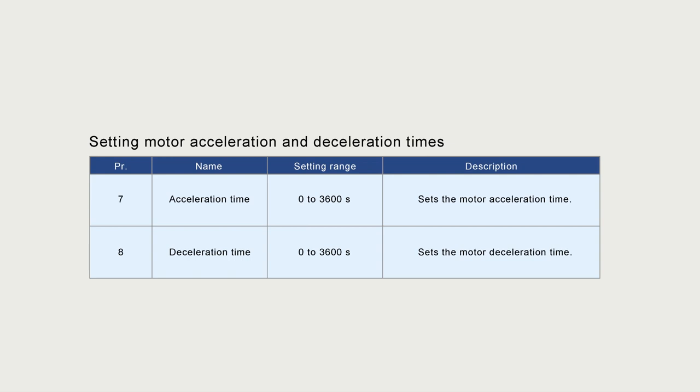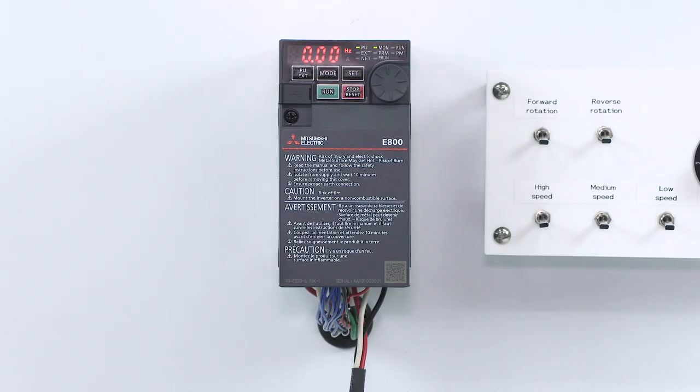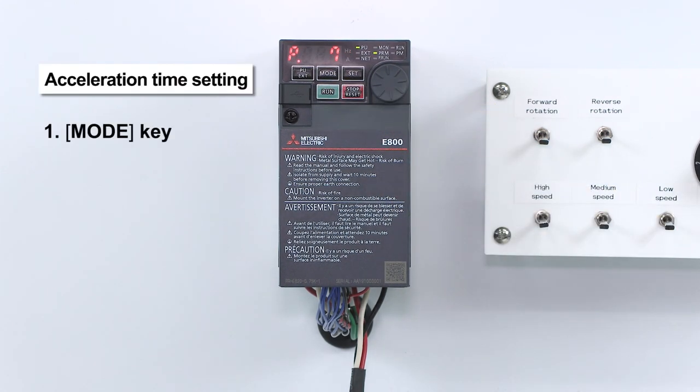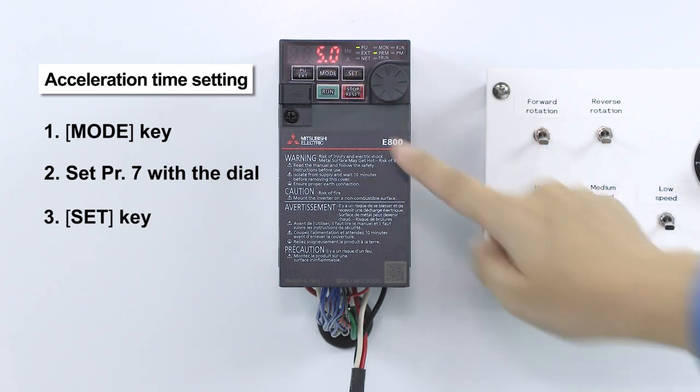Set motor acceleration and deceleration time with parameters 7 and 8. To set parameter 7, push the MODE key, select parameter setting mode, and turn the dial to 7.